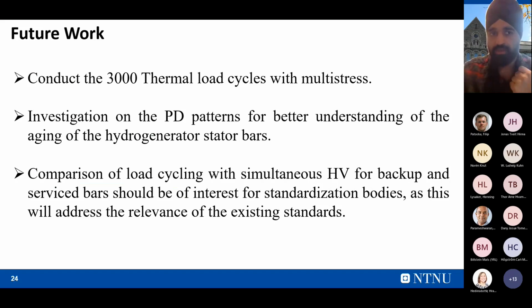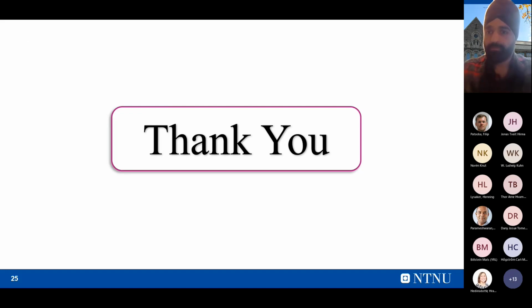So my future work is to conduct the 3000 thermal load cycles and investigate the PD patterns for a better understanding of the aging of the hydrogenerator stator bar, and also to compare load cycling with high voltage for the backup and service coil. This will be of interest to the standardization bodies, as it will address the relevance of the existing standards, because existing standards do not consider multi-stress testing. So that's all about this presentation.